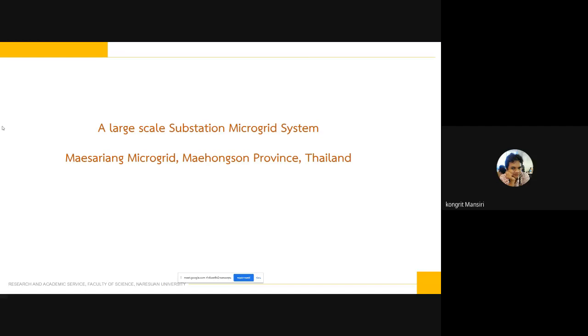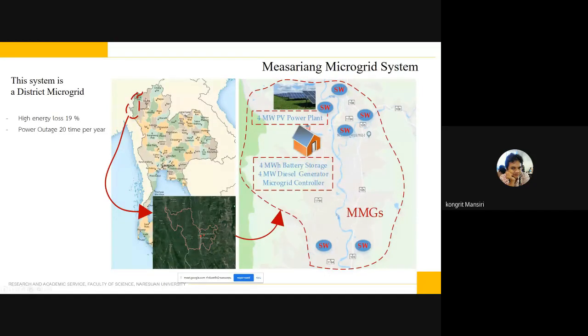It is a district microgrid system, a big system. Where is this? Here. If you see the picture, Mae Sariang district is in the northern part of Thailand, and the area is mountainous. Why did PEA, the Provincial Electricity Authority of Thailand, use this area for the pilot to implement the microgrid system? Because of high energy loss, about 19%, from the long distribution line. I will show you next. Also, there are power outages more than 20 times per year in this district, the biggest area.